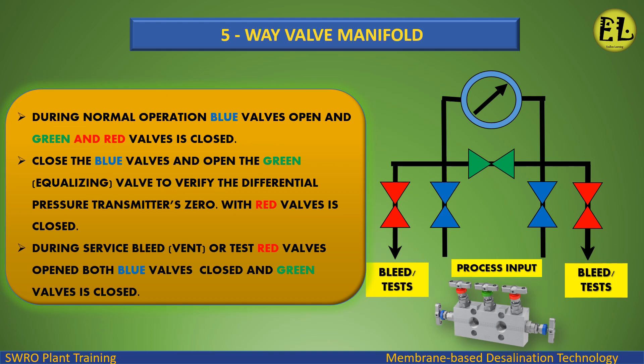During normal operation, the blue valves are open and the green and red valves are closed. Close the blue valves and open the green equalizing valve to verify the differential pressure transmitter's zero. During service — bleed, vent, or test — the red valves are open, and both blue valves and green valves are closed.